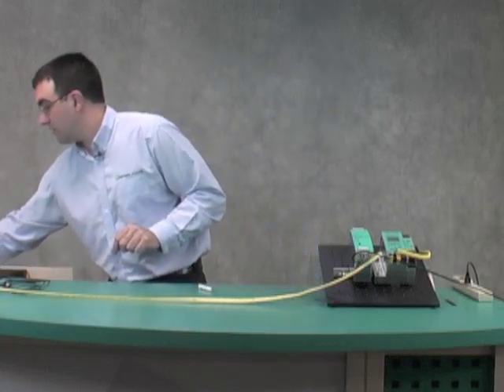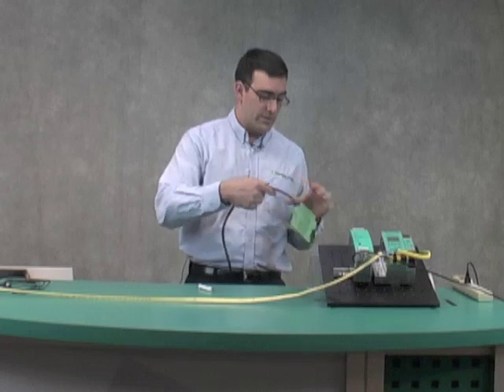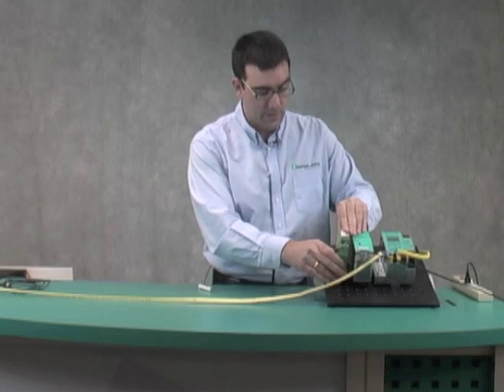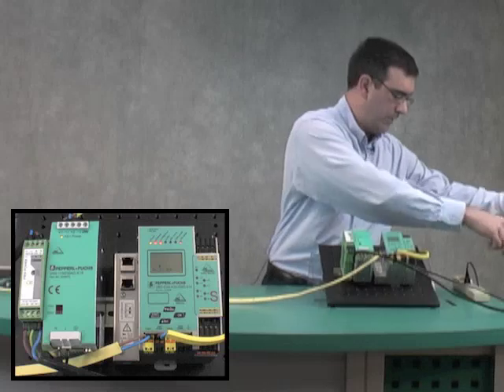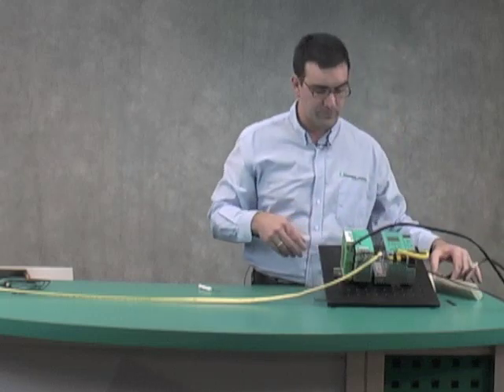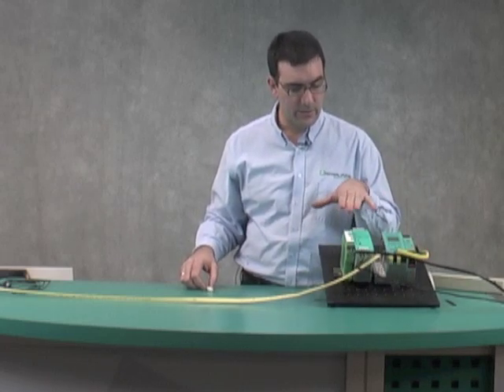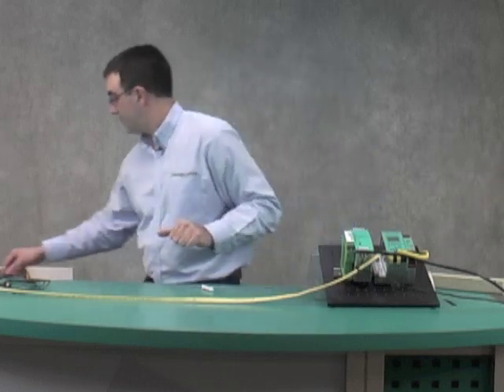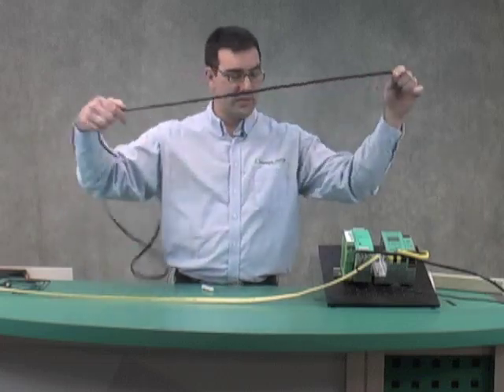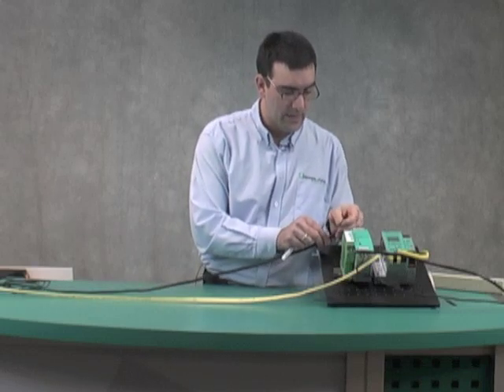The next thing we want to do is connect our auxiliary power. Auxiliary power is used for auxiliary inputs and for outputs on an ASI network. So we're going to plug this in. I've already pre-wired the 110 volts. All right, so that's done. And the next thing I want to do is put the flat cable on the power supply. Remember, the auxiliary power supply does not connect to the gateway at all. This is completely for the ASI network for outputs and that is about it.